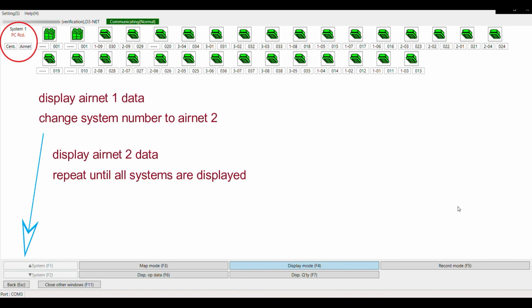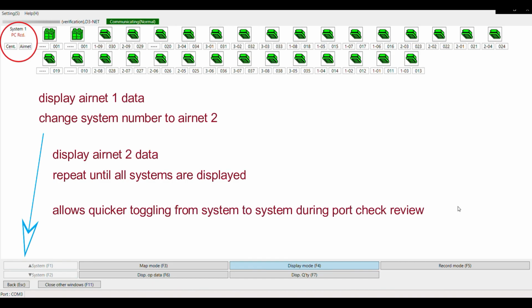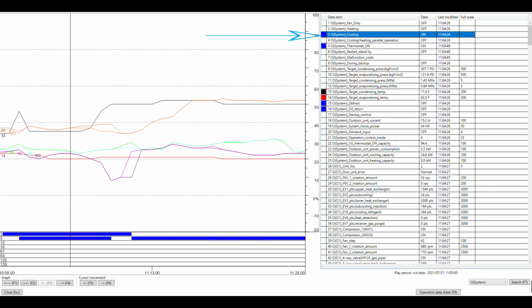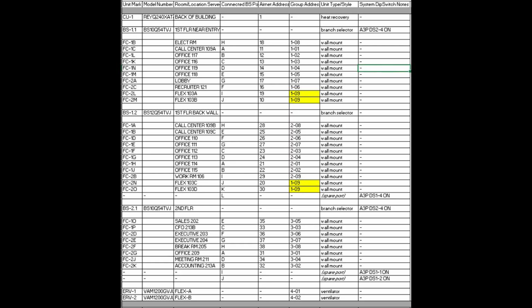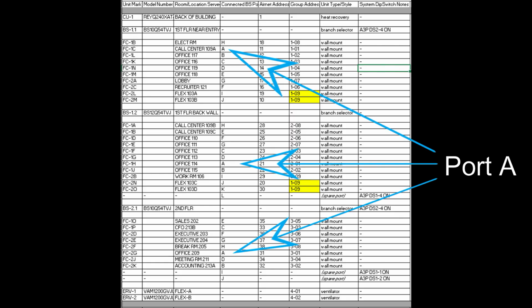This allows me to organize my data display windows and snap from system to system as I'm changing one unit on every box of every system all at the same time. So let's take a look at some operational data now and see what happens during the port check. Here you can see the entire system is in the cool mode. I'm going to switch over the first port of each of our three branch boxes now to the heat mode. That's port A for all three boxes.